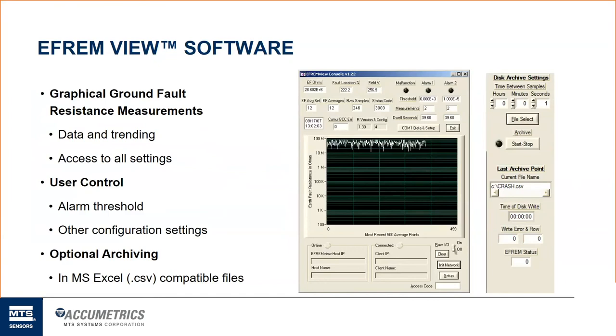So the user can then adjust some of the thresholds down in the bottom right corner. There's an access code, and this is detailed in the manual that every system would get. The access code is the same for every EFREM system. It's Tesla exclamation point, and that allows you to go into the setup and change those field resistance threshold values. Some users like to keep that a little closer together. So instead of 100K and 2K, they may opt for something like 60K and 20K. Again, that's totally customizable to each plant and how they choose to interface to that output.